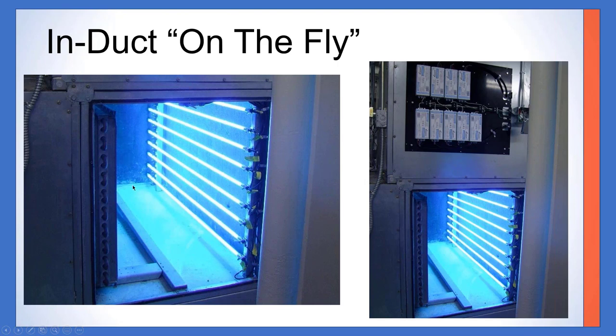So when designing systems for on-the-fly applications, you look at temperature and flow. We design them at end of lamp life, highest flow rate, lowest temperature. There were 1,500 lamps on that job, and the amount of energy was actually dictated by the military, who wanted a certain wattage. So it was quite a bit of overkill, about 72 watts per square foot, where coronaviruses and influenzas need around 30 watts per square foot, meaning you could take about half of those lamps out.